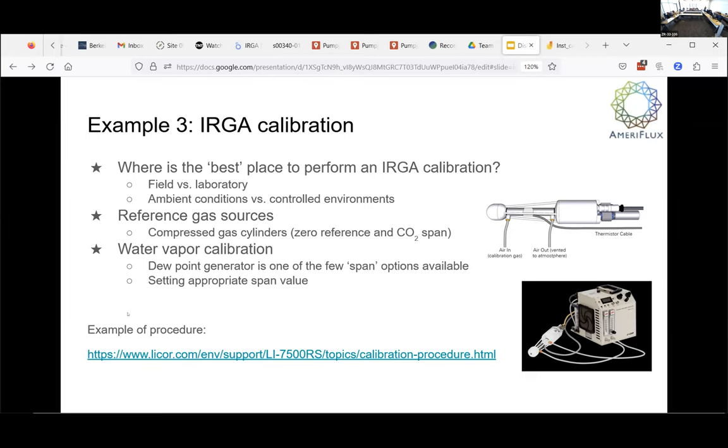That was online. Cassandra, we are now able to do isotope of CO2 calibration also, if you're interested. So feel free to ask about this. Well, I mean, that goes back to your point. Yes, use AmeriFlux gases because it's really hard to get good gases. In calibrating, you have to have a standard that you trust. That's right. You can calibrate with all sorts of things, and your calibration is only as good as your standard. So I think that's something you should leverage.